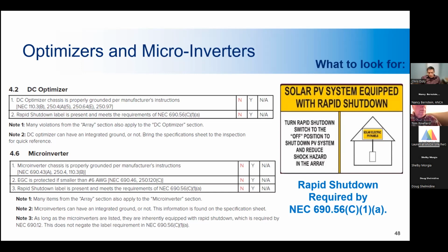This takes a lot of risk out. If there is a power outage or something, the conductors won't have DC electricity running through them, going essentially back to the grid, right? So to shock the people working on the power lines. And here's a snapshot of the proper labeling required to meet the rapid shutdown requirements for a microinverter or a DC optimizer.